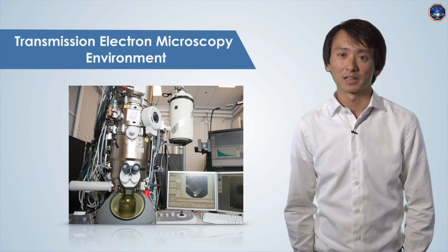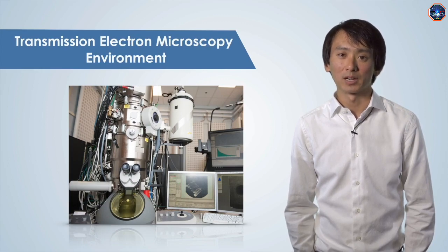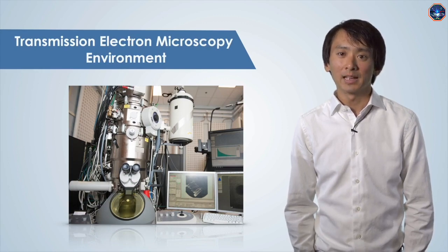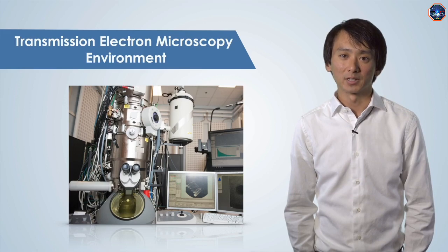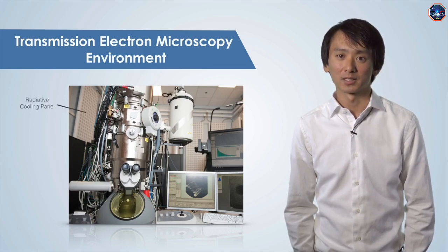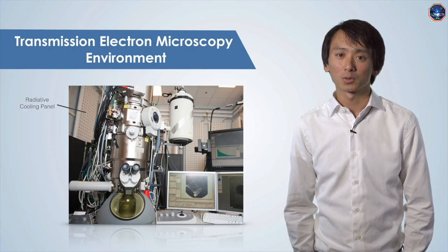Thus, TEMs are usually housed in basement rooms that have thick concrete walls, or are on floating tables that will automatically compensate for any building vibrations. As you can see in this image, radiative cooling panels can be used to keep the temperature constant. Water flows through these panels to help control the room's temperature.